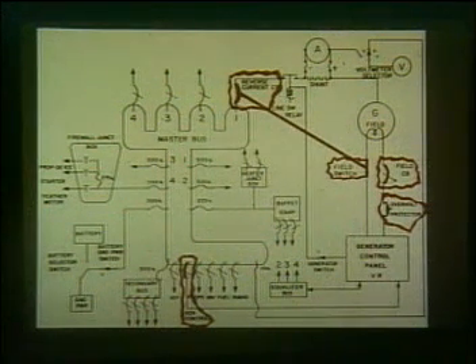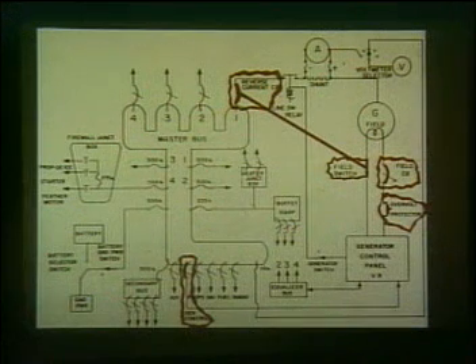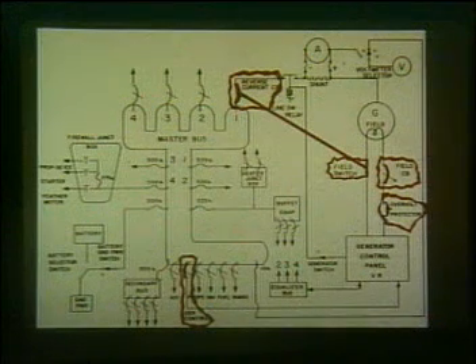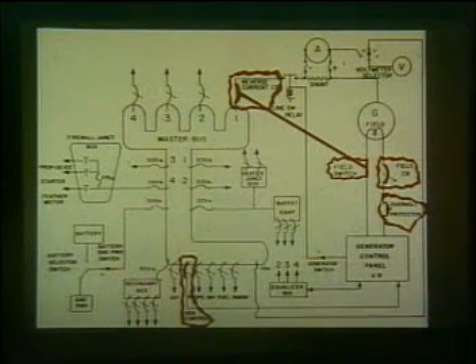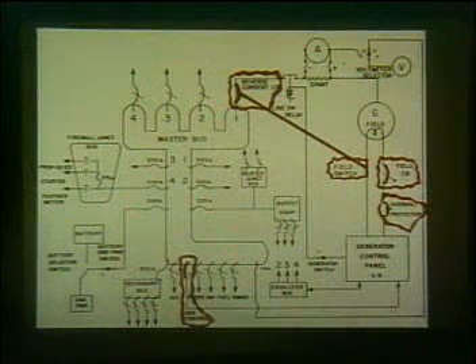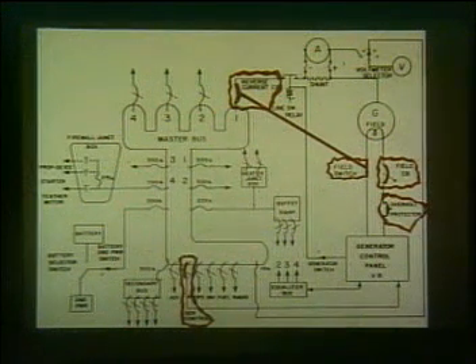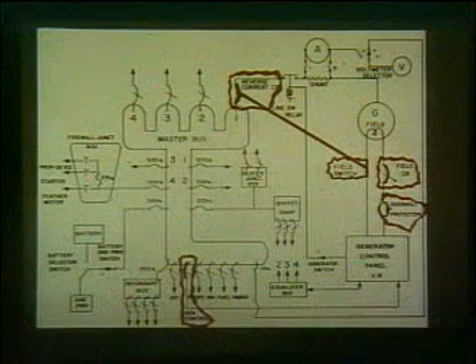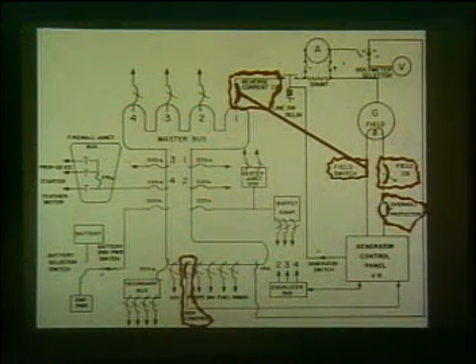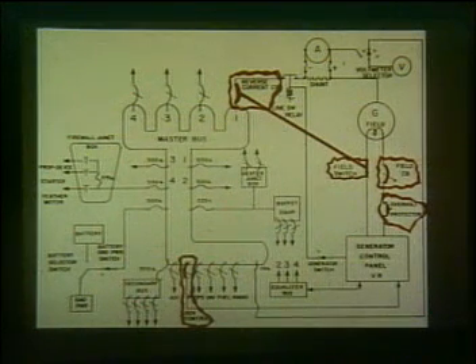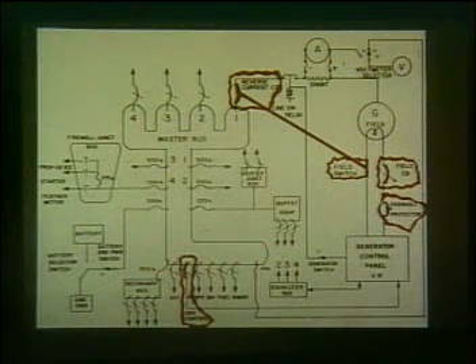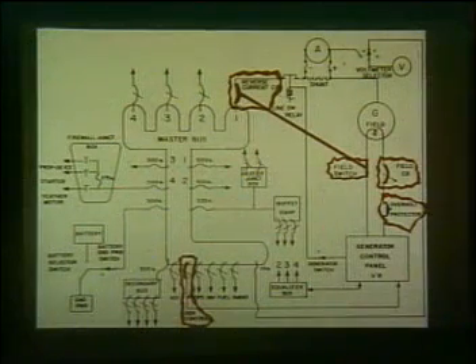Reviewing the protective devices in the generator output and control circuits, we find that any time the reverse current circuit breaker, overvoltage protector, or the field circuit breaker trips, they will open the generator field and remove the generator from the bus. If the generator field is opened, there will be no voltage or amperage output from the generator. The generator control circuit breaker protects the bus and the generator in the event of a malfunction in the generator control panel or generator.